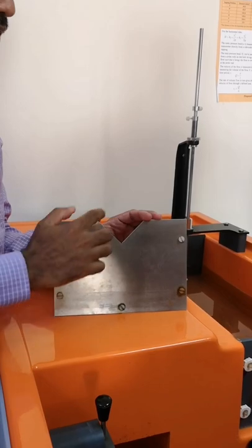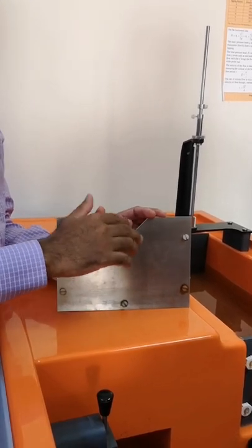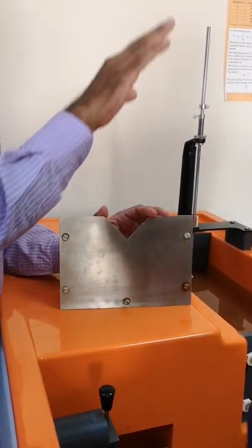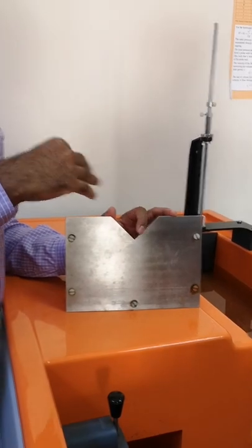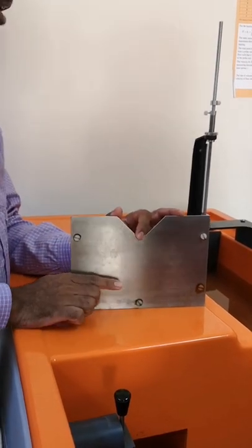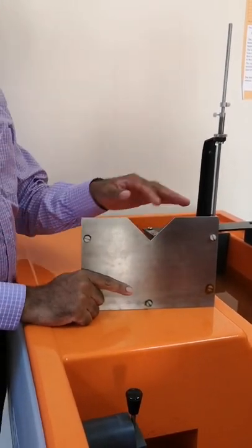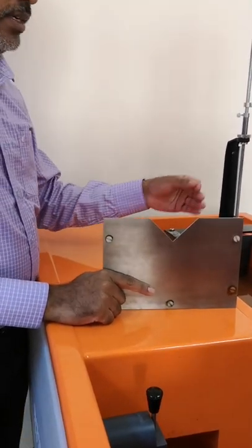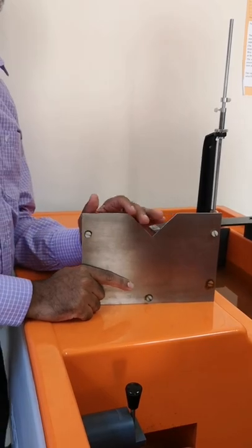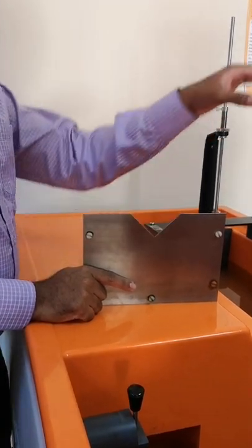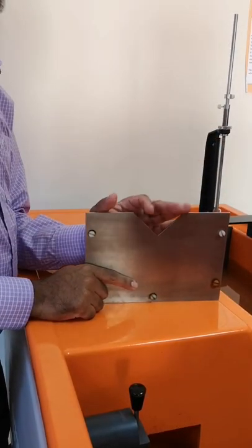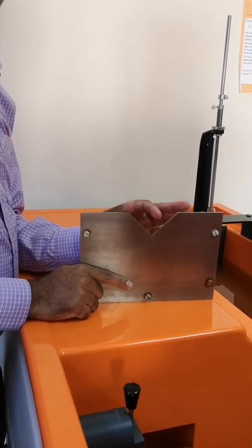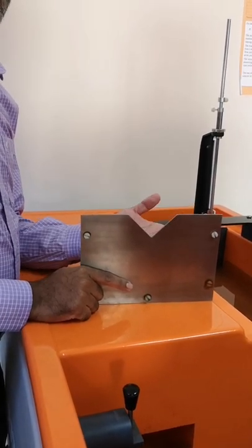First we need to determine the coefficient of discharge. Once we know the coefficient of discharge, there is an equation. Using that equation, we can directly determine the flow rate when we know the height. The height can be easily measured. Normally now we have an ultrasonic sensor. If you fix the ultrasonic sensor, it will measure the height very accurately. Once you know the height, you can easily calculate the flow rate.